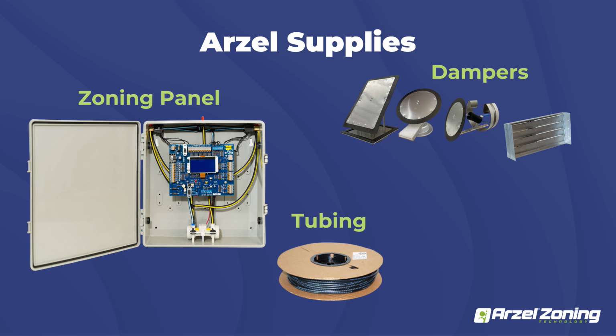And then typically, if you aren't doing trunk dampers and you're doing branch style ductwork, where you have an individual damper in each run of that home, you're also going to need our T's, which are our fittings there in the bottom right-hand corner. You don't need any other tools as far as the tubing is concerned. Just a pair of PVC cutters will work to cut the tubing. The fittings themselves are barbed fittings, so you don't need hose clamps or anything. You just slip the barbed fitting into the tubing, and that's how the dampers will actually connect to the system.